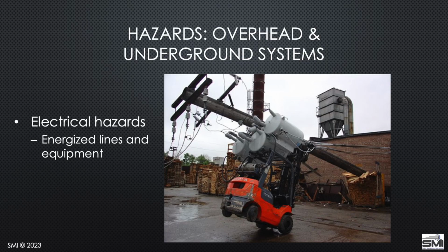Some overhead and underground system hazards: energized lines and equipment. You can see here where this pole has fallen on a forklift. If you're the forklift driver, first off, you were lucky you had a good headache rack. But getting off, if the forklift is in contact with energized conductors, and you step off, you can see the ground around it is very wet, so you'd be at a different electrical potential. We always tell people who are on fire to drop and roll, but if you're on this, you want to jump off, not step off, and then shuffle your feet until you get away, because there might still be a potential ground grid.